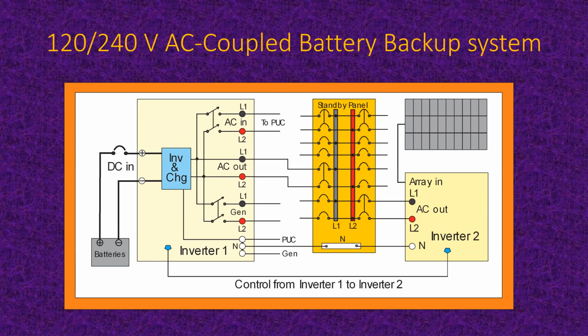Case number 2, utility is there, it's nighttime. Well, we're not making any solar electricity now, so that means utility has to provide all of the power to the main distribution panel, which is not shown on this slide, plus the standby panel. And that goes through L1 and L2 at the top, through that double pole switch up there, down to the AC out, and into the standby panel. And if the batteries need a little charge, the inverter will charge them until they're charged, and then it'll stop. That's case number 2. These cases, by the way, are listed, I think, on the next slide, but it's a whole lot easier to understand them if you're looking at the picture.